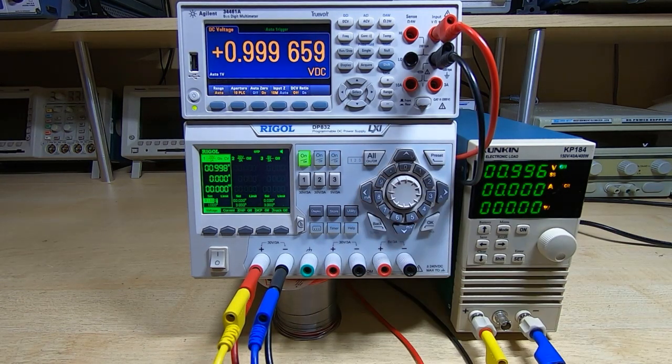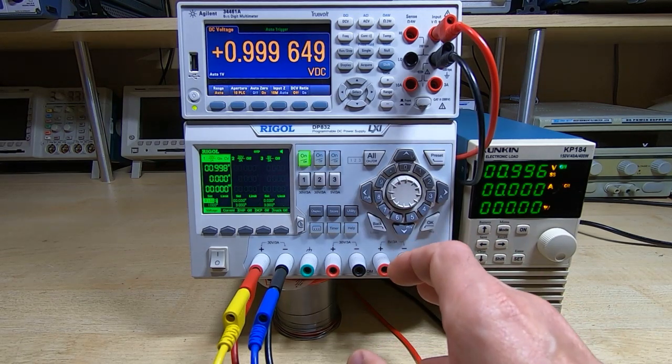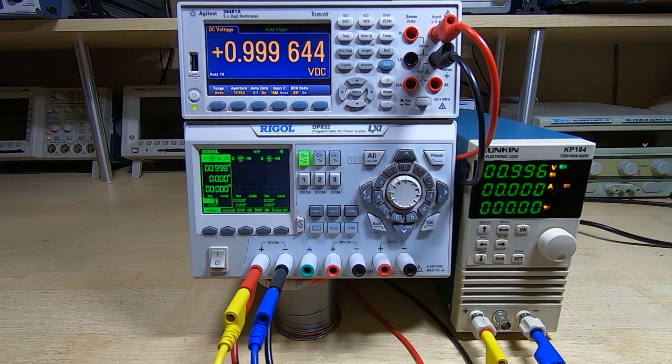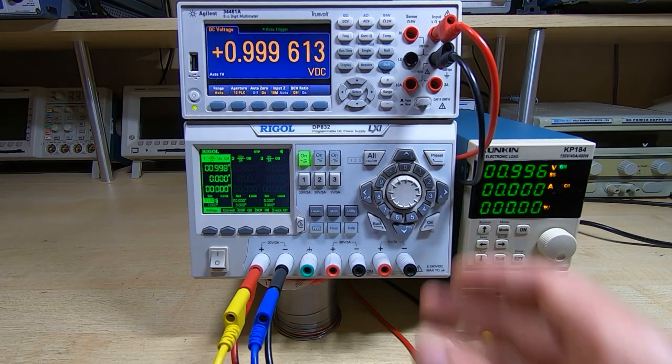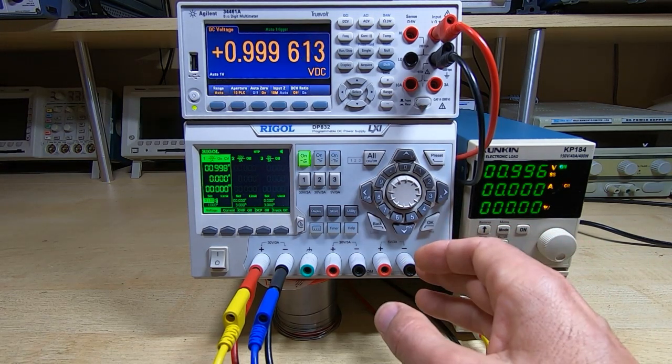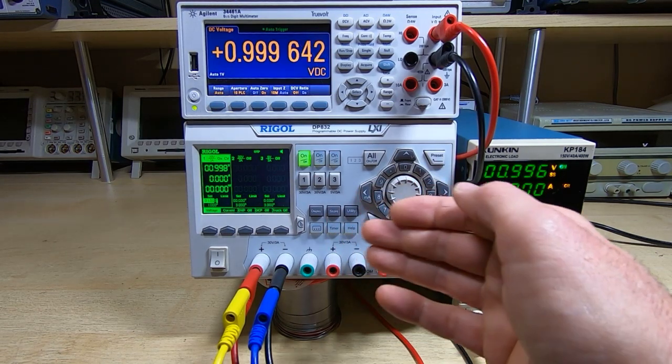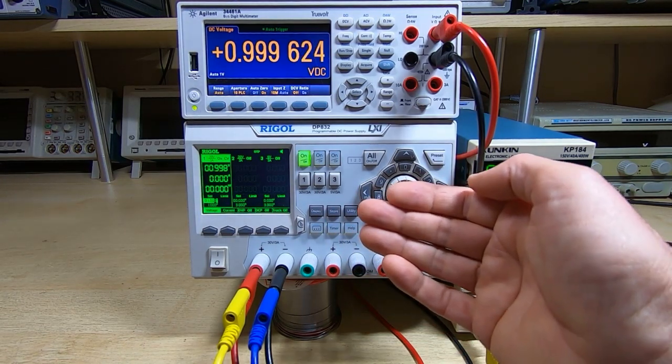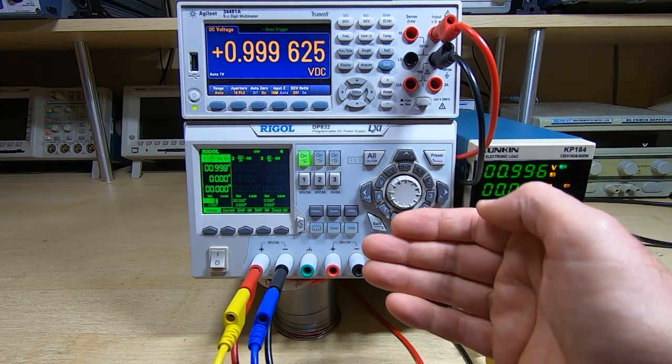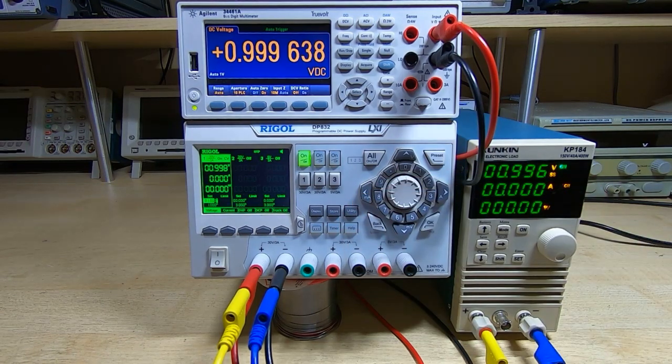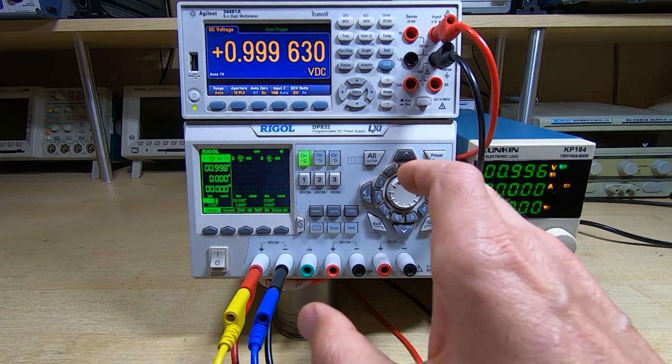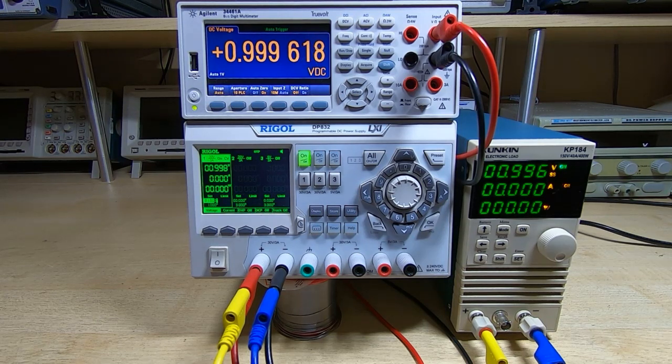Either way, if you have a Rigol DP832 and you've got this problem of it constantly resetting itself, then if you watch my previous videos in this series, it's a very easy fix to apply. You can do it in just 15-20 minutes. You don't need to take the entire front board out; you can just unscrew the front panel, fold it down, and then solder the capacitor in place. As I say, it does seem at the moment to have been a 100% successful repair.